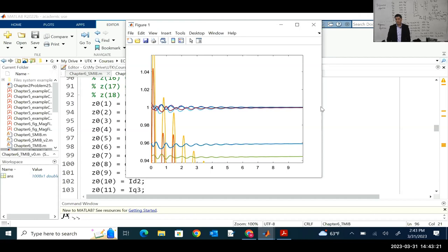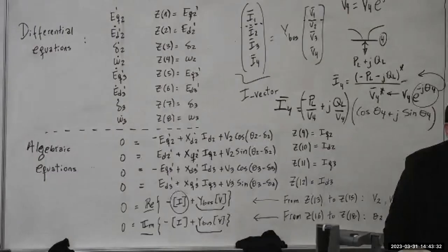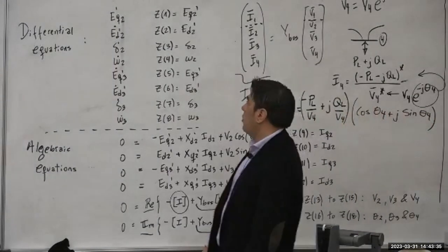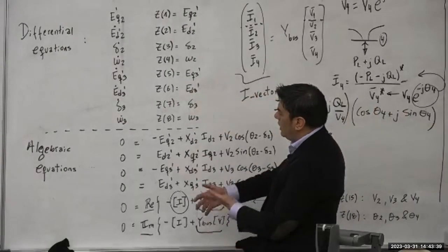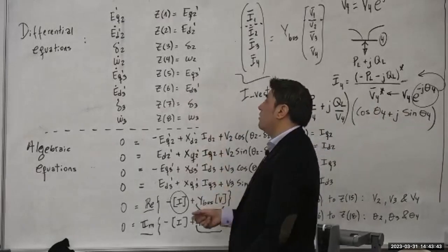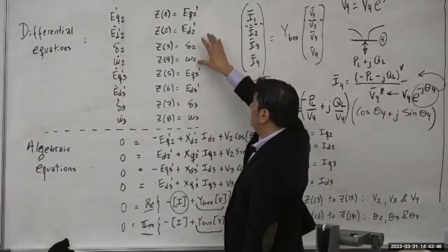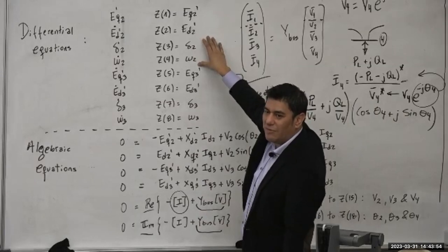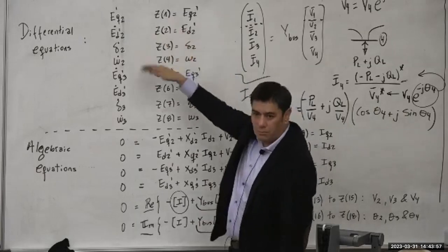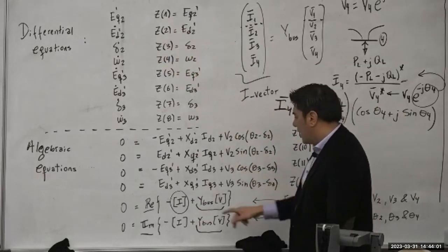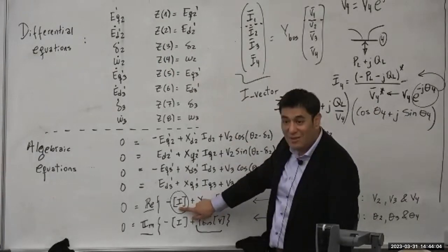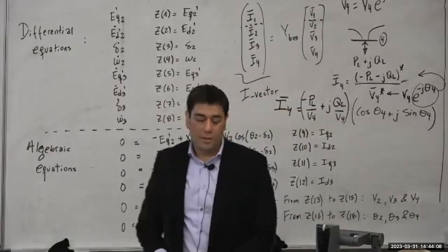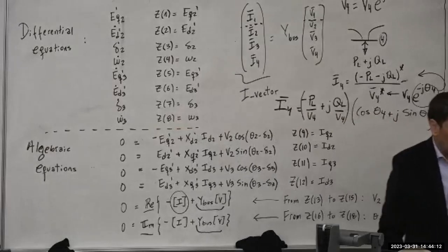In a system with an infinite bus, frequency won't deviate because the infinite bus holds it. But in a finite system with only generators with inertia, a generator trip causes a large power removal, a power imbalance, and frequency deviation. We could study that disturbance when we add the governor to the generation. To impose a generator trip in this code: isolate the generator equations so they're disconnected from the rest, set the injected currents to zero, and the system handles it.